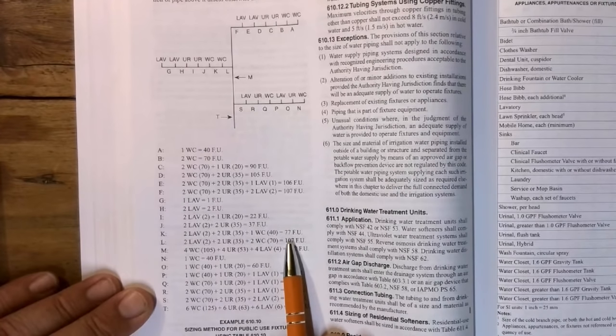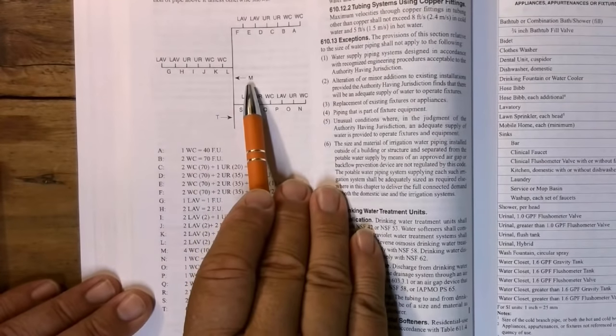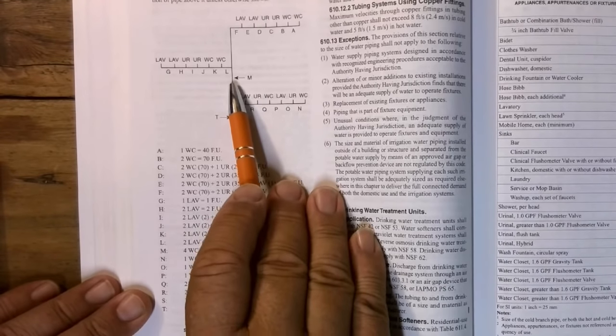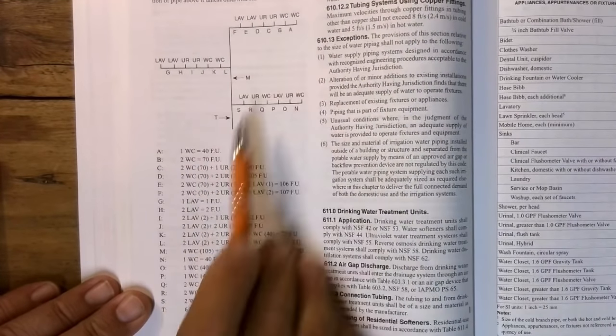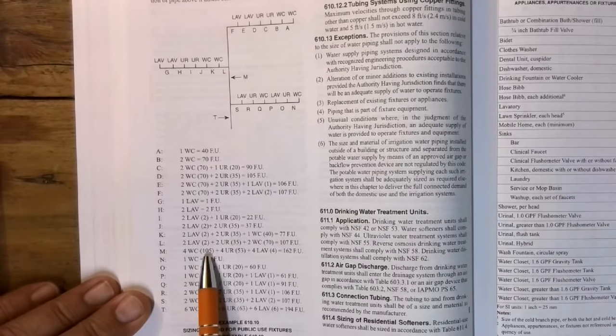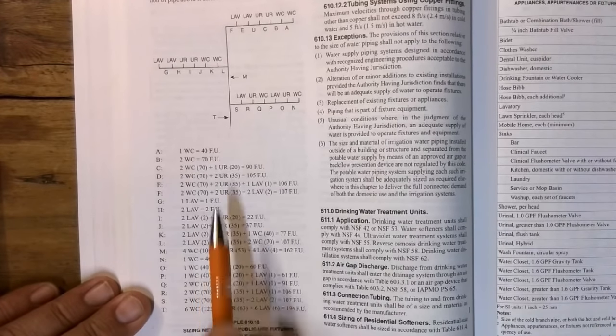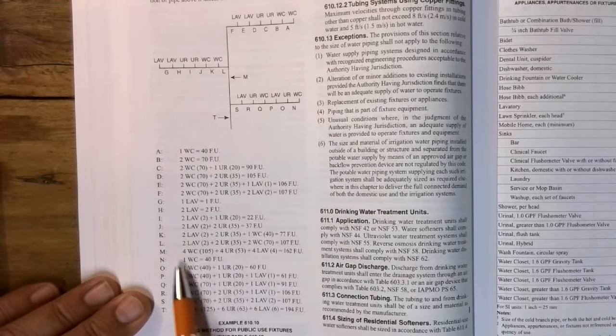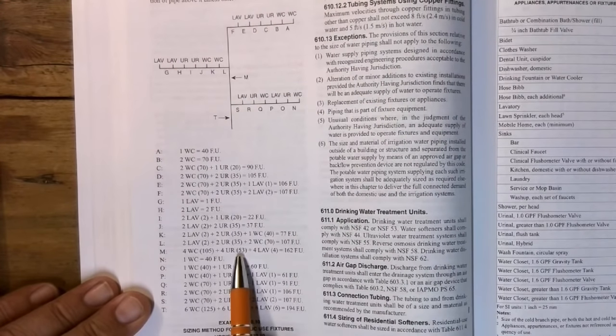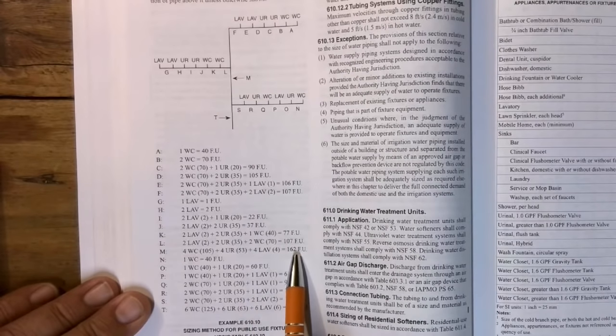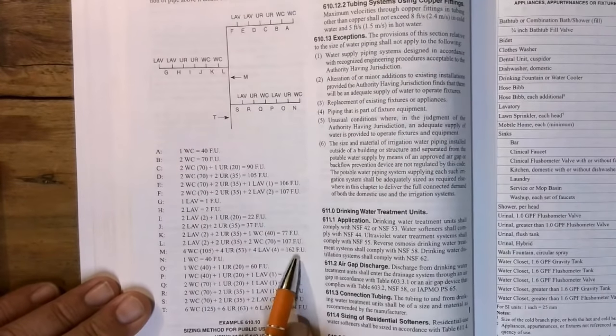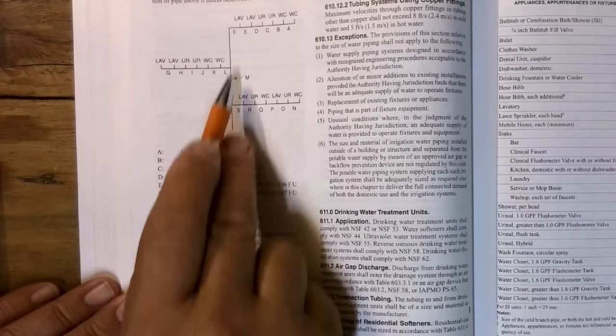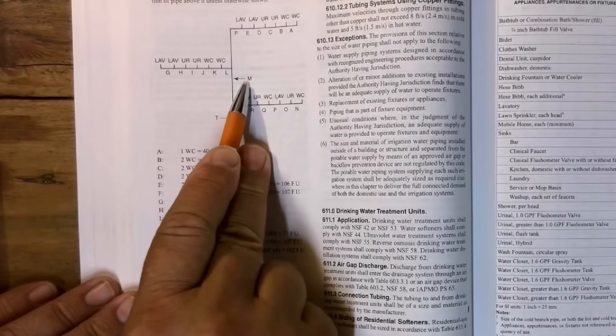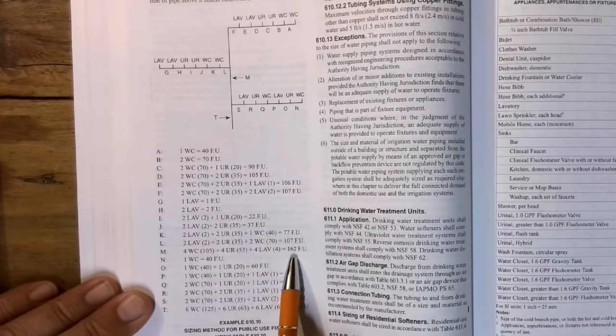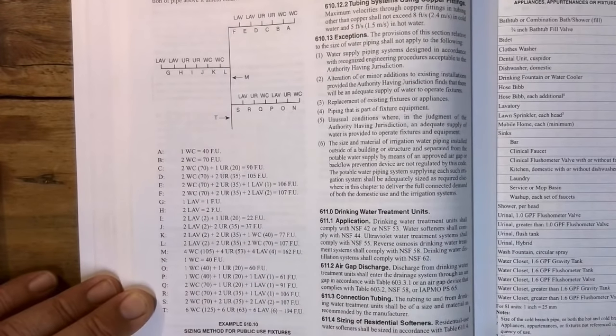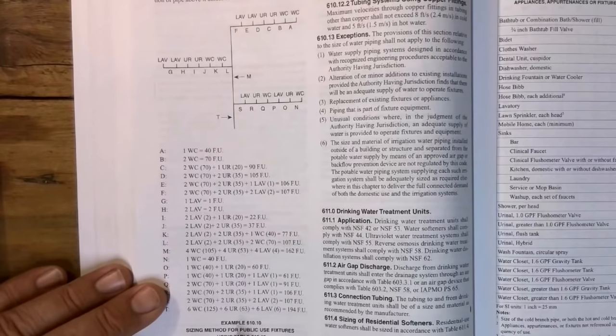But let's go to M, okay? So now we go to M. How many water closets are on M? One, two, three, four. So for M, four water closets, that's a total of 105 fixture units. How many urinals? Two, four. Four urinals, 53 fixture units. Four lavs, 162 fixture units. So now you got 107 here and 107 here, so you would think this would be 214, but it's not. It's only 162 because you're adding everything up and it's decreasing in value, okay?